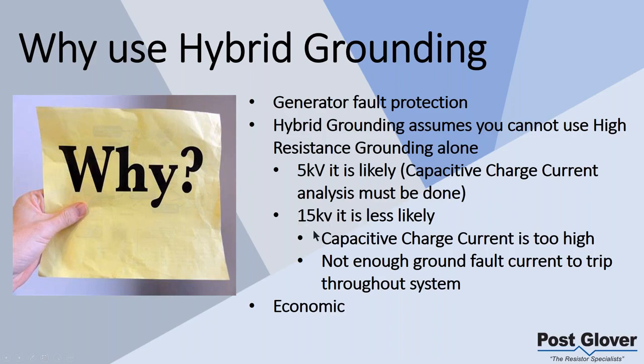At 15 kV, that is less likely. You're not going to probably use high resistance ground in the traditional sense. I mean, you could definitely use it, but for two reasons. One, the capacitive charge current is too high, if you're looking for continuous operation. It's too high to operate a high resistance ground system.